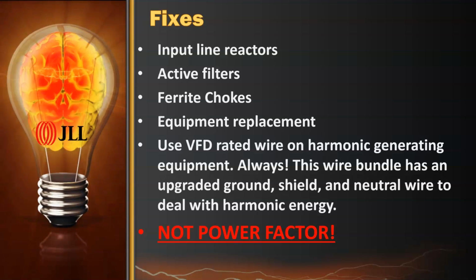The wire bundle's got an upgraded ground. It's got a really good shield in it. Neutral wire is very well insulated, and the ground is insulated as well, and it actually is quite a bit larger. There are internal shields on those as well. And so then that increased energy created by the harmonic is going to be absorbed by that shield, and it'll just kind of make that problem go away. Belden makes pretty good cable like that, and so do the other manufacturers, VFD rated wire.